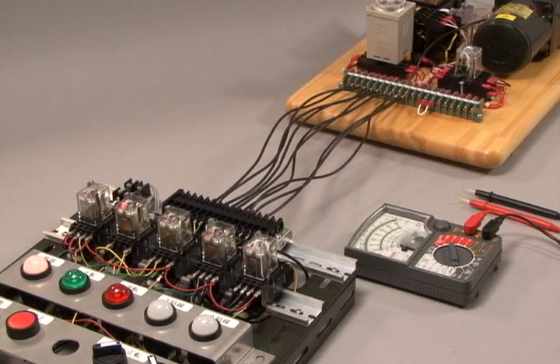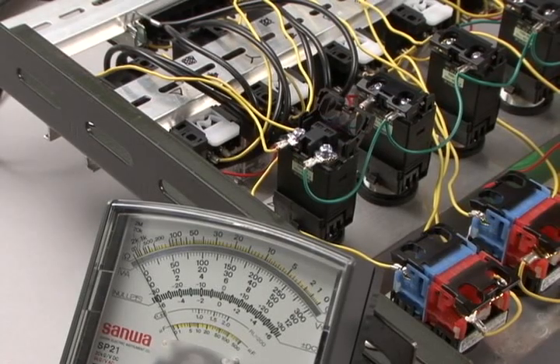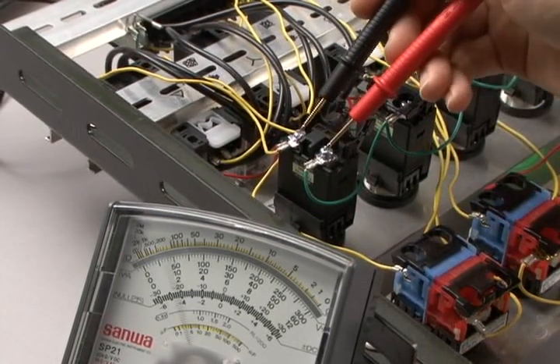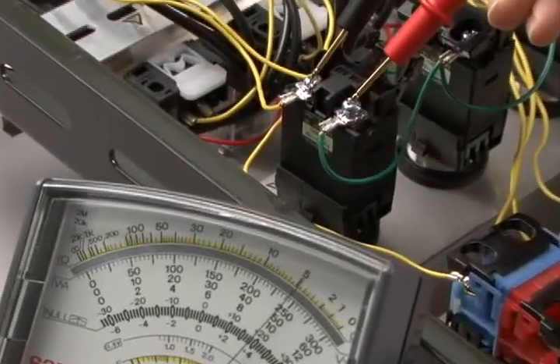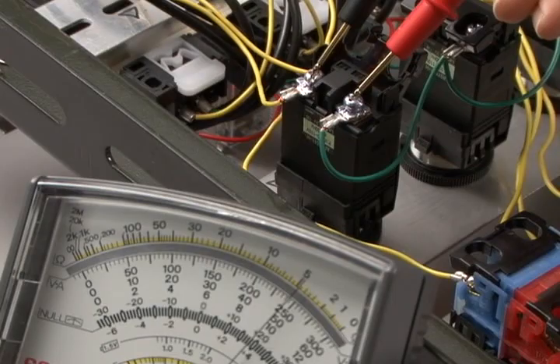In the event that cables connecting the terminal board with the white power source lamp have become disconnected, then while the MCCB is switched on, measure the voltage between the terminals of the white lamp. If the measured value is normal, the cables are not disconnected. If it is not normal, the cables may be disconnected.